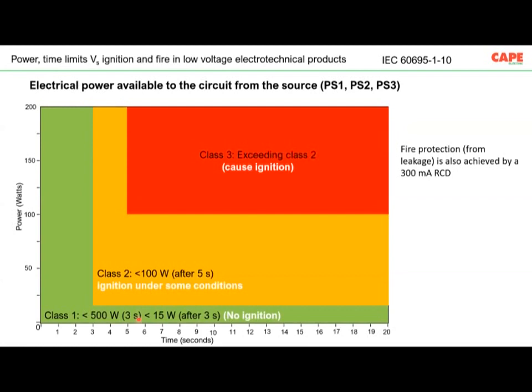This kind of power supply is not supposed to ignite a fire under normal conditions. Power supply class 2 means a power supply which is reducing the fault to less than 100 watts within 5 seconds. Under this condition, ignition is very much limited. Ignition is not so common. Power supply class 3 can ignite fire. So power supply classification is very much necessary, especially for an equipment, let us say for an air conditioner.